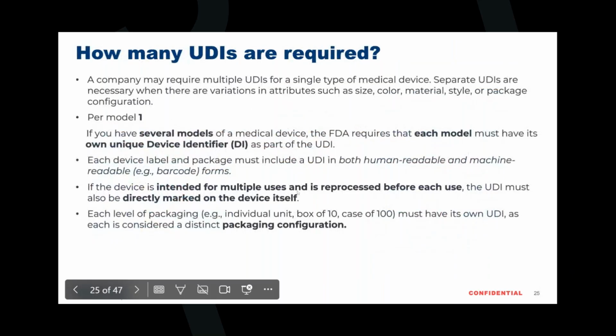How many UDIs are required? Okay, so it's important to keep in mind that each model, each version of your device, if it changes in sizes, in colors, anything different in it, requires its own separate UDI. If you have large gloves and small gloves, each size requires its own UDI. A company may require multiple UDIs for a single type of medical device. Separate UDIs are necessary when there are variations in attributes such as size, color, material, style, or package configuration. It's per model. If you have several models of a medical device, the FDA requires that each model must have its own unique device identifier.